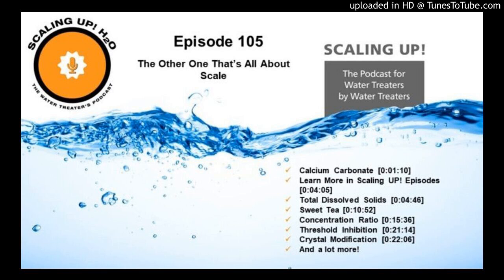And then we look at the 5 components that make up calcium carbonate, and then we can do something with each one of those to reduce the likelihood that we would scale. So we might want to control pH, and you might have a system out there that's using acid to suppress the pH. You might have a water softener that takes the calcium out of the water. Maybe you have a dealkalinizer and you're taking some of the alkalinity out.